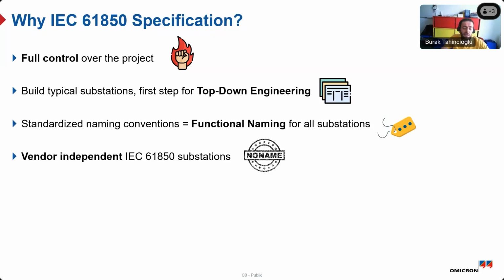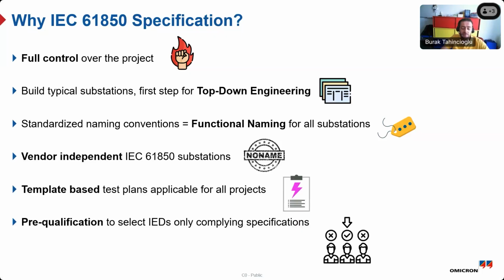As we build many substations, with renewables and battery energy systems coming in more and increasing the number of substations, we want standardized naming conventions in 61850-based substations. Many substations have been digital for a while, but some have different namings; we want functional namings that allow a utility-wide naming convention across the entire grid. We want this functional naming applied so that at the end we have a vendor-independent 61850 substation, a typical substation valid for all future substations.